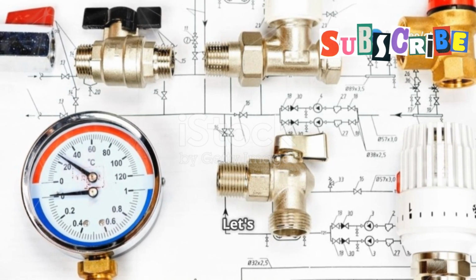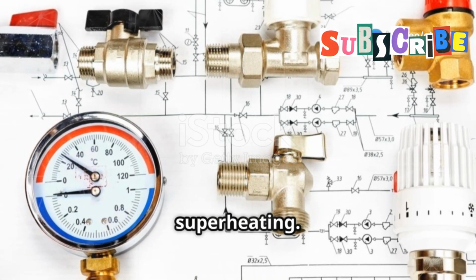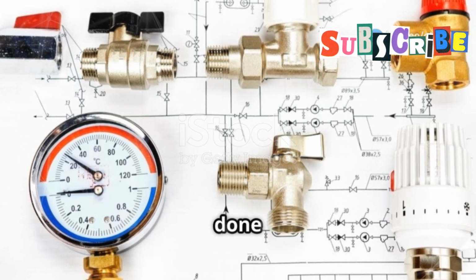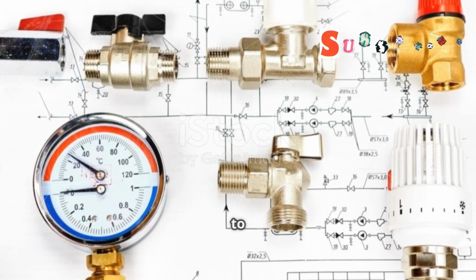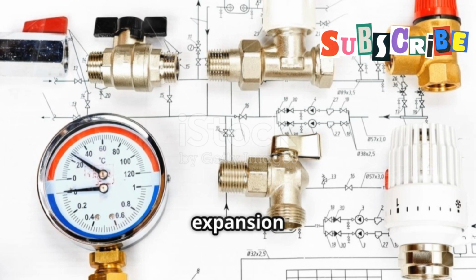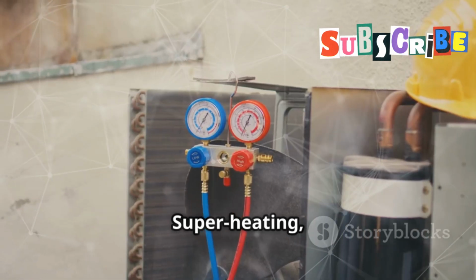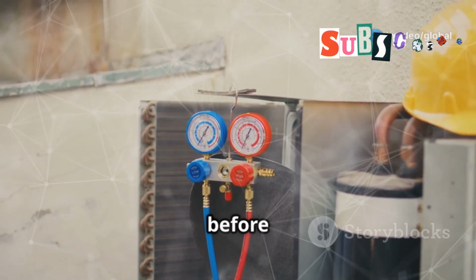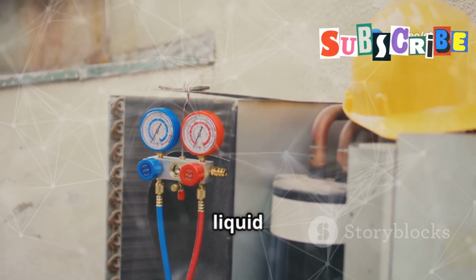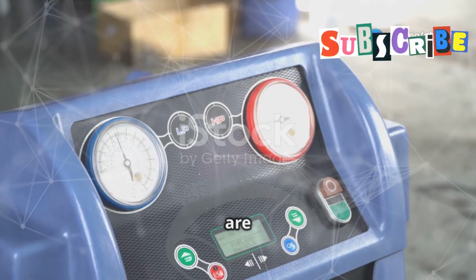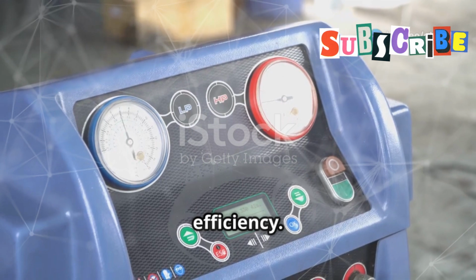Handy little unit. Let's move on to subcooling and superheating. Subcooling is done before expanding the refrigerant to ensure no vapor enters the expansion valve. Superheating, on the other hand, is done before compression to make sure no liquid enters the compressor. Both are crucial for system efficiency.